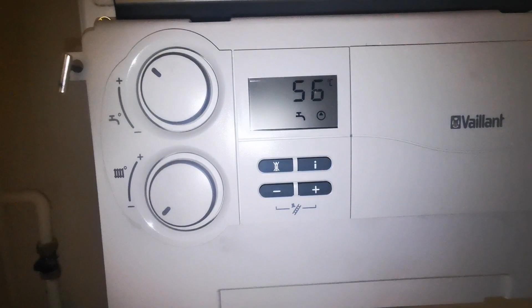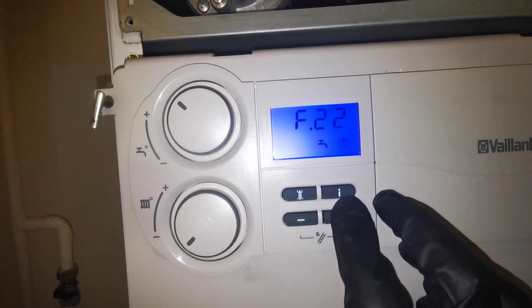Hey, it's Gold Gas. This series is going to show you how to view the faults memory to see the previous fault codes or error codes that have occurred in this boiler. Press the I and the minus key together and then the fault codes will appear. You've got the last 10 on here and you can scroll through them with the plus and the minus key.